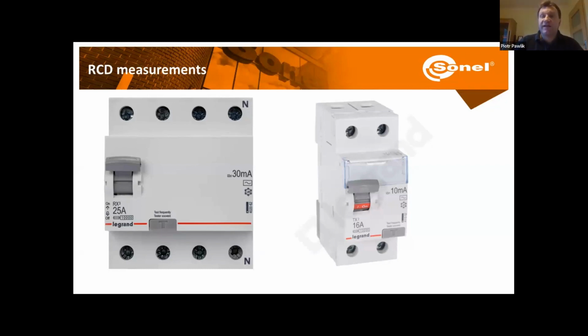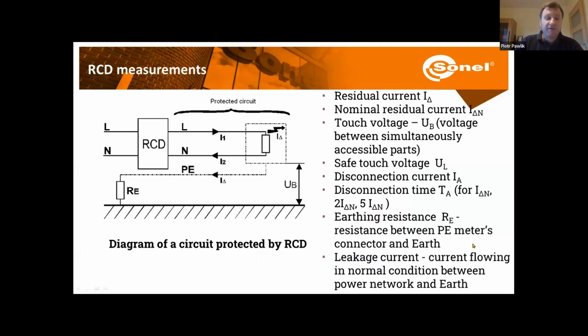Okay, and finally, let's move on to the measurements of the RCD parameters. So how does it work? Well, we put the RCD between phase and neutral channels, or between all three phases and the neutral. And if everything is fine, the current flowing through the phase channel powers the device, and the same value of the current returns through the neutral channel. The RCD sees that there are no differences between the current flowing in on a phase and flowing out on the neutral, so it will not trigger.